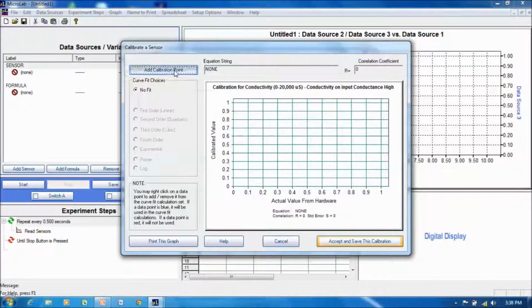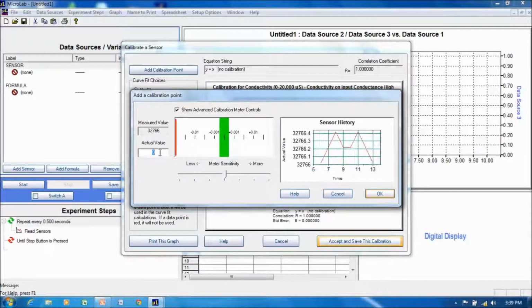We're going to add a calibration point, and the first point we're going to use is with deionized water. So I'm going to put this on the stirrer, turn the stirrer on. I've got it set to some moderate value, and I'm going to lower the conductivity probe into the deionized water, and I'm going to check to make sure there are no bubbles. I've got all the bubbles out by jiggling it around. Deionized water at 25 degrees Celsius, which is the room temperature today, has a conductivity of 0.05 microsiemens, practically 0.